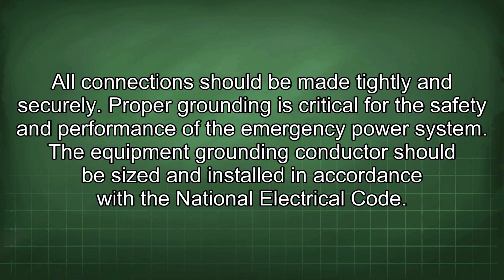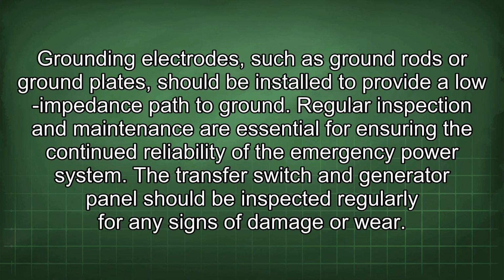Proper grounding is critical for the safety and performance of the emergency power system. The equipment grounding conductor should be sized and installed in accordance with the National Electrical Code. Grounding electrodes, such as ground rods or ground plates, should be installed to provide a low impedance path to ground.